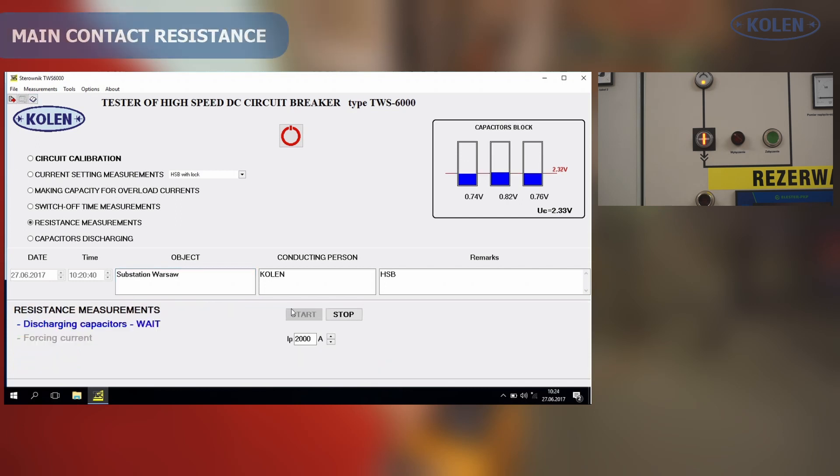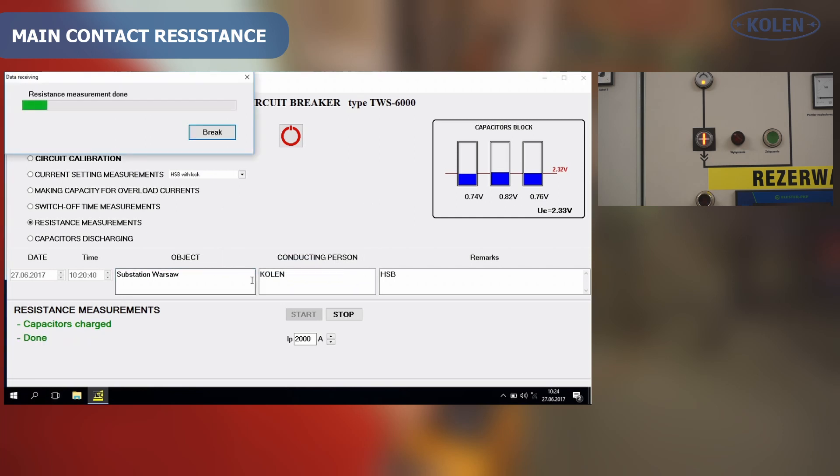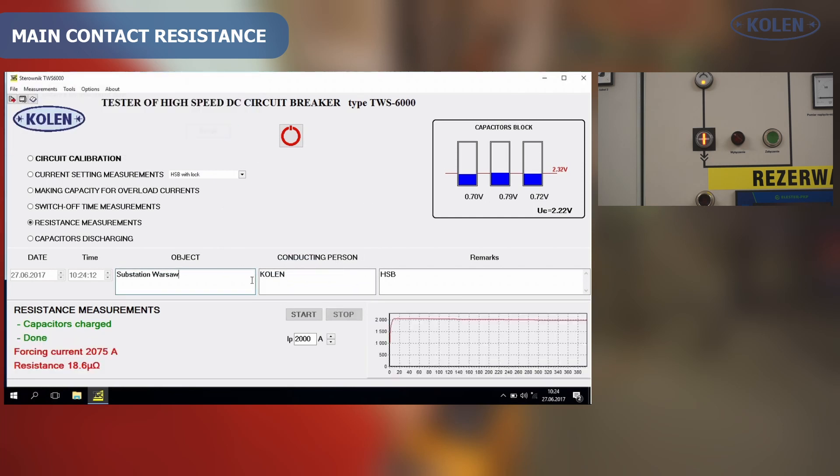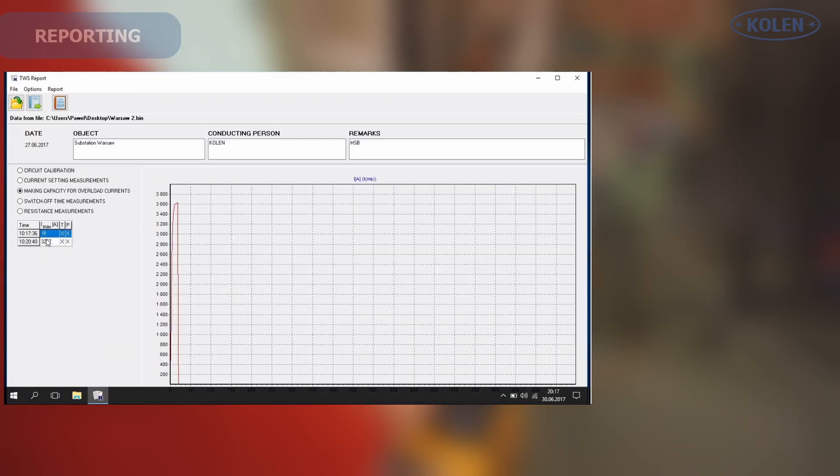Tester is capable of accurate HSB contact resistance measurements. This resistance should not be higher than the value specified by the breaker manufacturer. Tester is capable of electrical connection resistance measurements in high current circuits with a resistance value from a few micro-ohms.